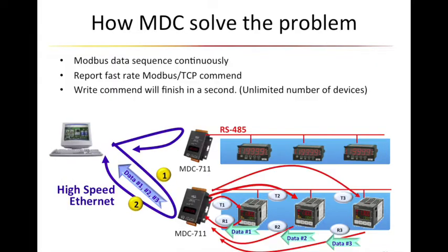The Modbus data concentrator will use a scan engine to read back the data of Modbus RTU devices one by one, and store the data in the internal memory of the MDC device. After receiving the Modbus TCP command sent from the PC, the MDC will then directly send the data stored in its internal memory to the PC. Therefore, when the PC requires the data of the Modbus RTU devices, it can communicate with the MDC through the Ethernet. The communication speed will be fast and all the data stored in the MDC can be retrieved immediately at once. In this way, it is much more efficient.